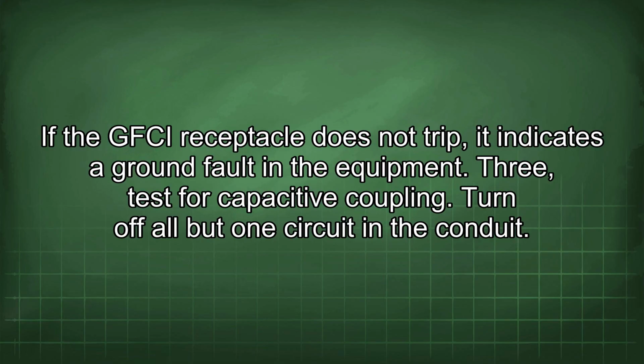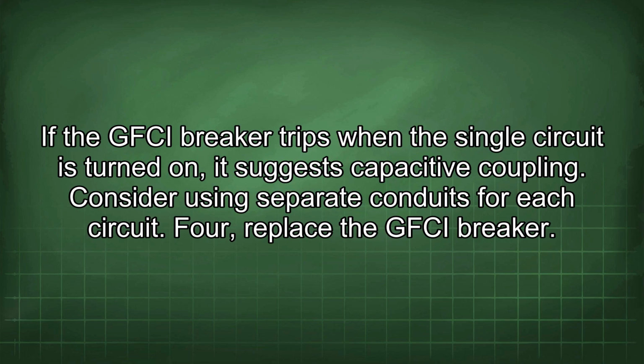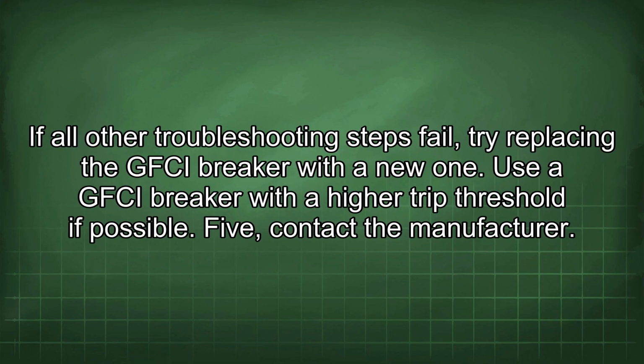3. Test for capacitive coupling. Turn off all but one circuit in the conduit. If the GFCI breaker trips when the single circuit is turned on, it suggests capacitive coupling. Consider using separate conduits for each circuit. 4. Replace the GFCI breaker. If all other troubleshooting steps fail, try replacing the GFCI breaker with a new one. Use a GFCI breaker with a higher trip threshold if possible.